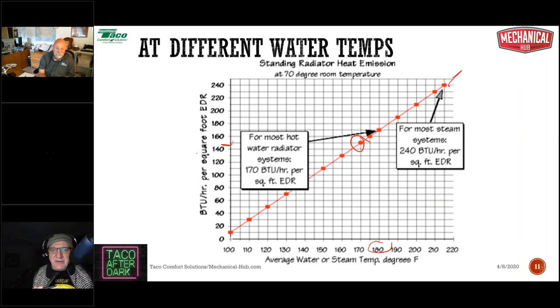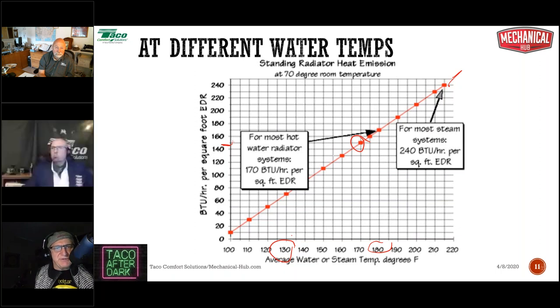So that went down what looks to be about 15 BTUs per square foot, a 10 degree drop in average water temperature. 15 BTUs per square foot worth of EDR was lost. Now, if we were to look at a modulating condensing boiler and we wanted to use an average of 130 degree supply water temperature under design conditions, we can go back over here and see we're now at about 70 BTUs per square foot of EDR. So water temperature affects the cast iron radiators, obviously, very, very much in terms of output because it's mostly radiant. There's very little convection going on here.